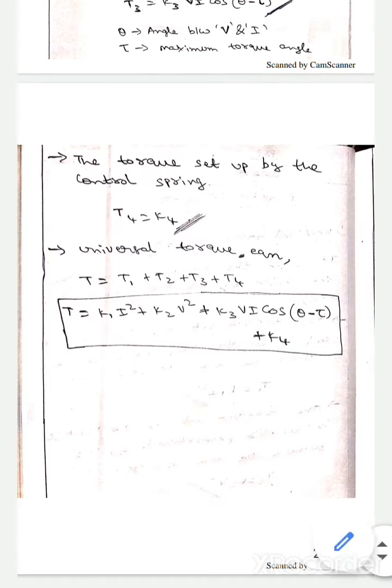Whereas T3, it is the torque set by both voltage and current coils and it is directly proportional to the product of voltage and current and also cos of theta minus tau. Here theta is the angle between v and i, whereas tau is the maximum torque angle. Here T4, it is the torque set by the control spring and it equals to k4.